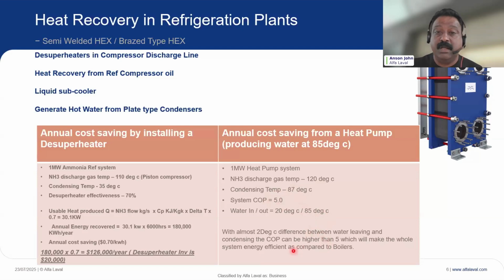And as compared to hot water generated by the boilers, it's going to bring at least 20% of energy saving. CapEx is going to be a bit higher if you're going for a new heat pump, but if you've got an existing refrigeration system with a piston compressor, it makes a lot of sense to add a condenser, which can work at a high condensing temperature and generate hot water from the system.